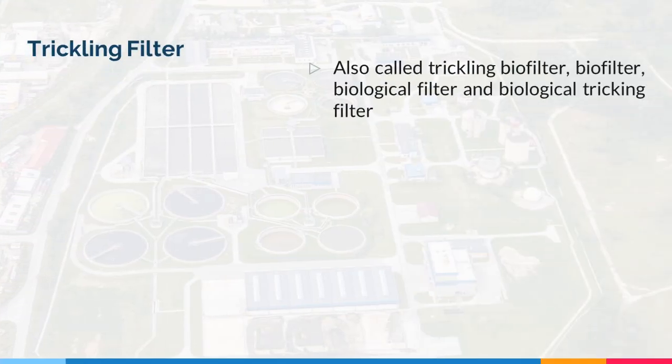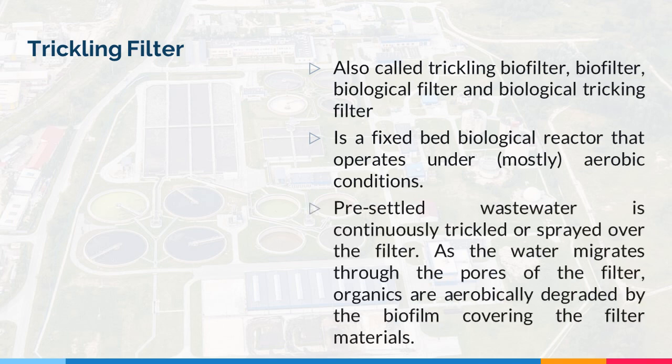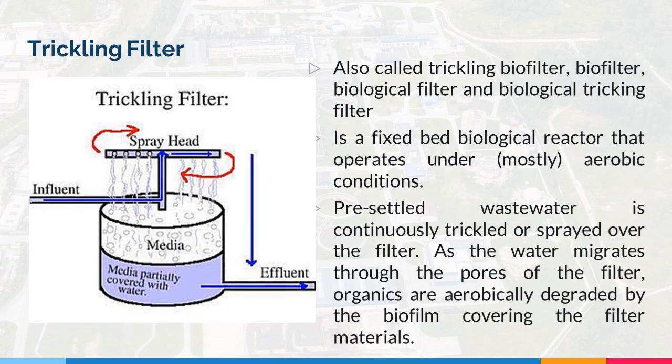Next, we have the trickling filter, also called the trickling biofilter, biofilter, biological filter, and biological trickling filter. It is a fixed bed biological reactor that operates under aerobic conditions. Pre-settled wastewater is continuously trickled or sprayed over the filter. As the water migrates through the pores of the filter, organics are aerobically degraded by the biofilm covering the filter materials.